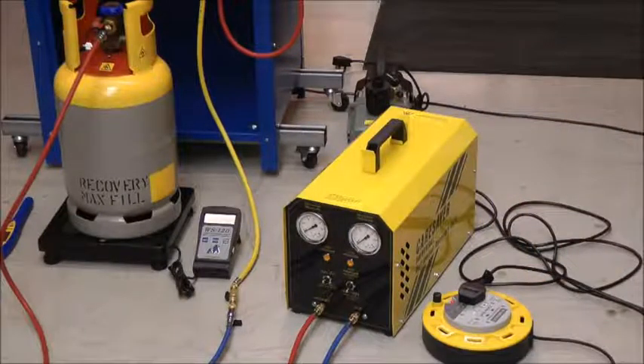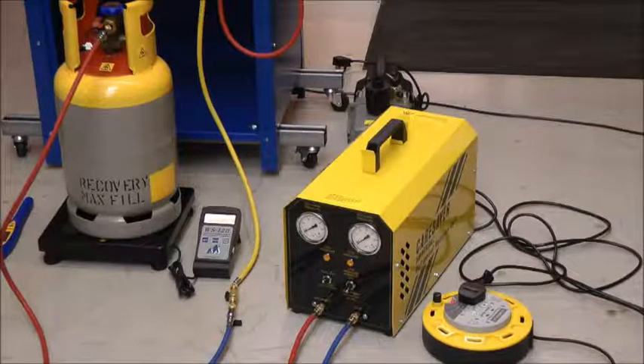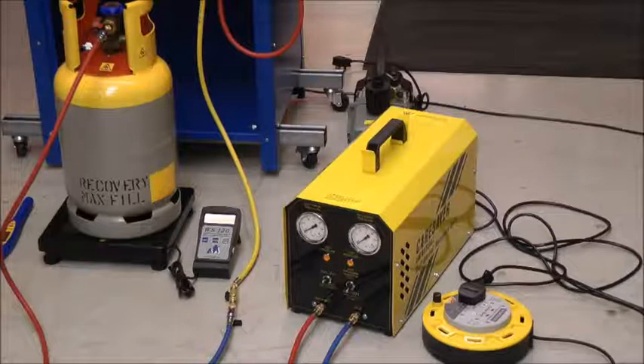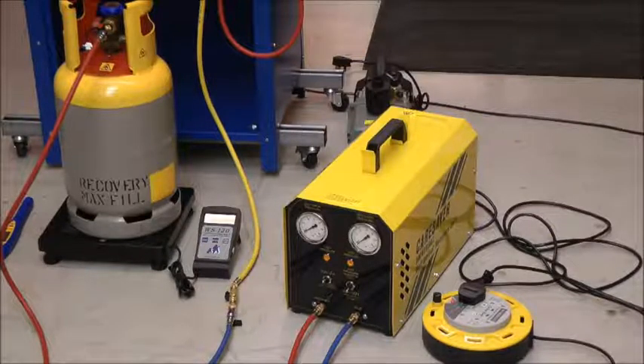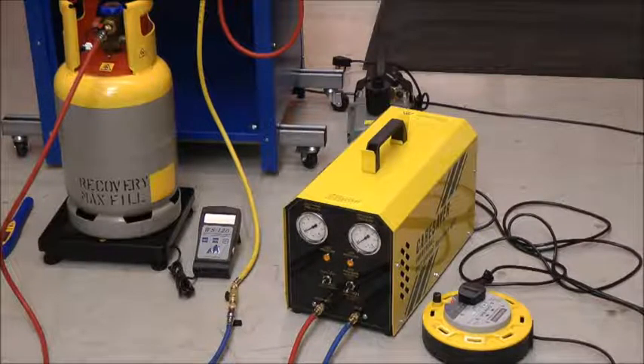The CareSafe hydrocarbon recovery machine doesn't have an on-off switch. It is powered directly from the 13 amp socket and we must ensure that the extension cable is switched remotely outside the three meter working zone. In our case here, the machine will be plugged in and you will switch it on and off from the wall socket, which is outside of a potentially flammable zone.